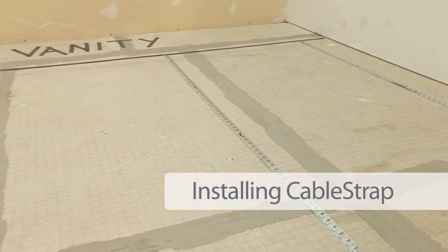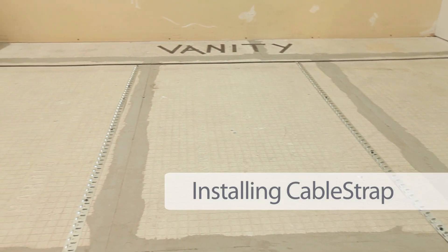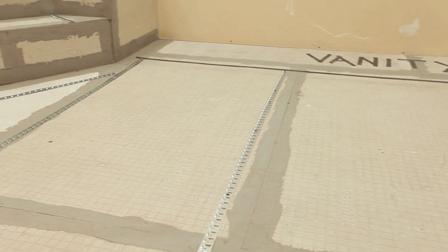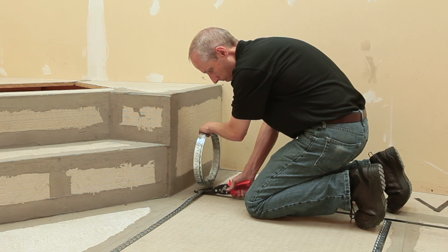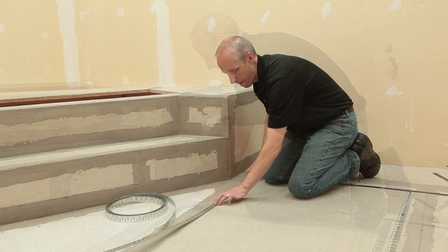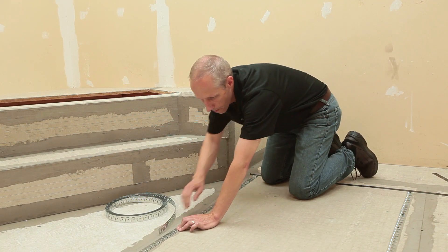Start by installing the cable strap at each end of the space wire will span between. Leave a path for the wire from the thermostat location to the closest strap. Cable strap can be cut using metal shears. Place strapping at the edge of the toe kick in front of sink cabinets.